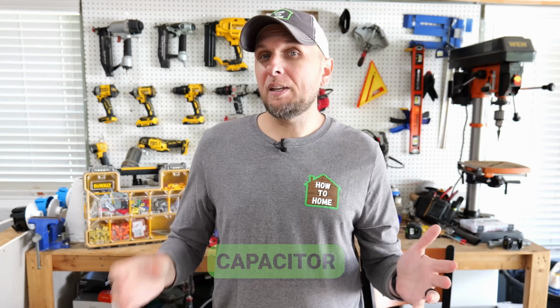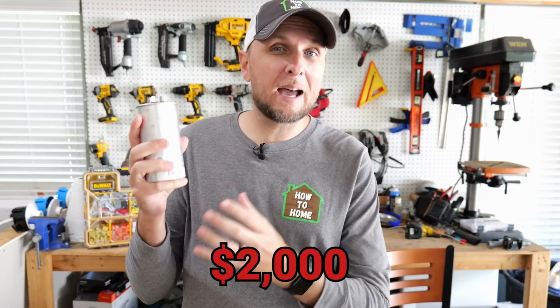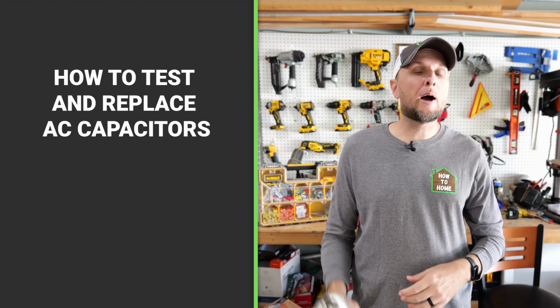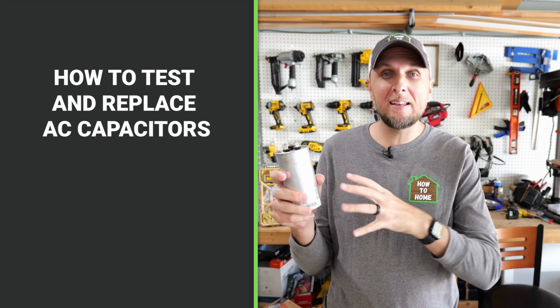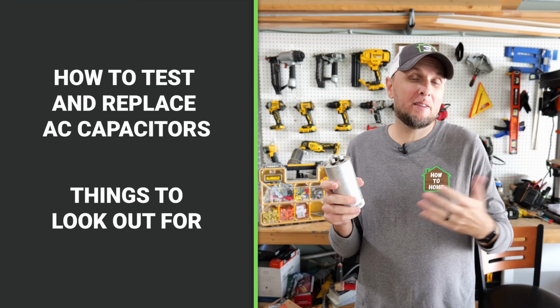There's one particular item I think all homeowners should at least be aware of, so they know what to look out for, especially as we get into these warmer months and the AC unit is going to be running more. The most common issue I see with AC units, and the biggest scam I see committed by some HVAC companies, comes down to your capacitor. I've seen people charged up to $2,000 to replace this $10 to $20 part. In this video, I'm going to show you how I go about testing and replacing these, and some things to look out for in the event this happens to you.